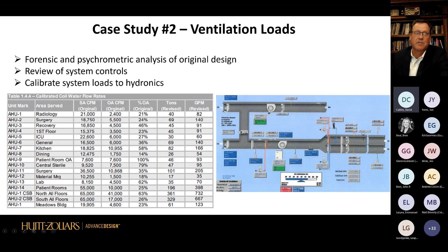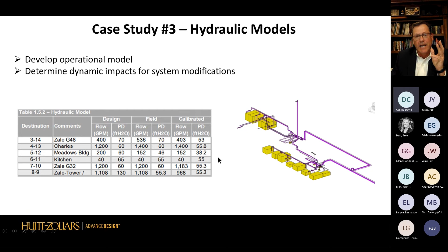So again, now our hydraulic model, and we're going through, and now that we know all the fittings, and we look at the original design, and we went out and looked at the field conditions, we can now start calibrating our model with the friction factors. And now we have a calibrated model. And now that we have the model, we can go through all the electric and gas bills, and we normalize this through the actual weather data of that time in 2019. And now we can get to the load calc.